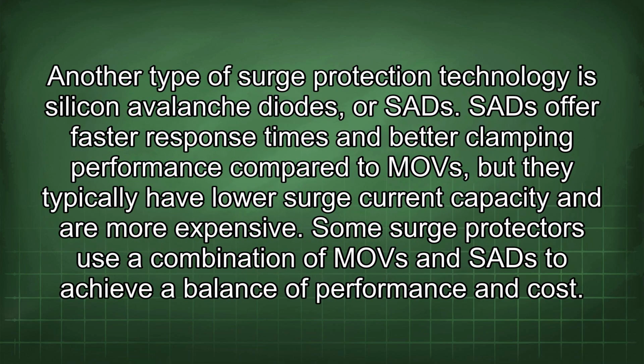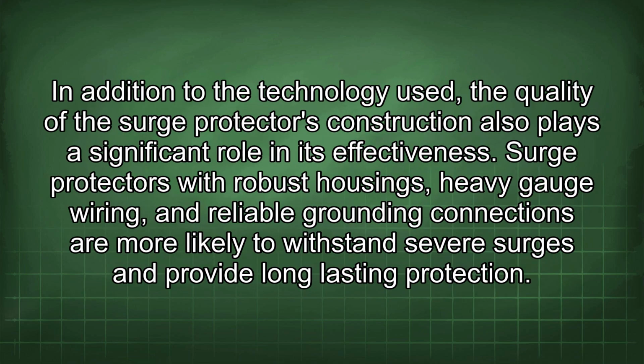Another type of surge protection technology is silicon avalanche diodes, or SADs. SADs offer faster response times and better clamping performance compared to MOVs, but they typically have lower surge current capacity and are more expensive. Some surge protectors use a combination of MOV and SAD to achieve a balance of performance and cost. In addition to the technology used, the quality of the surge protector's construction also plays a significant role in its effectiveness.